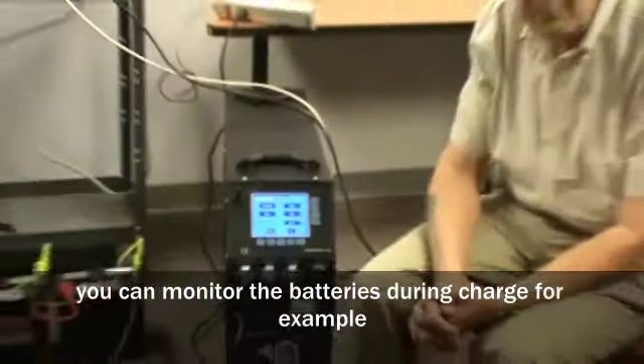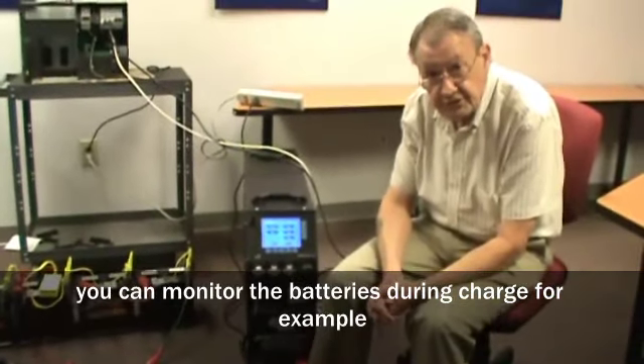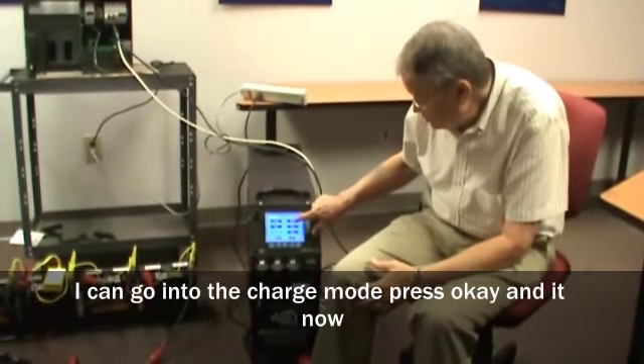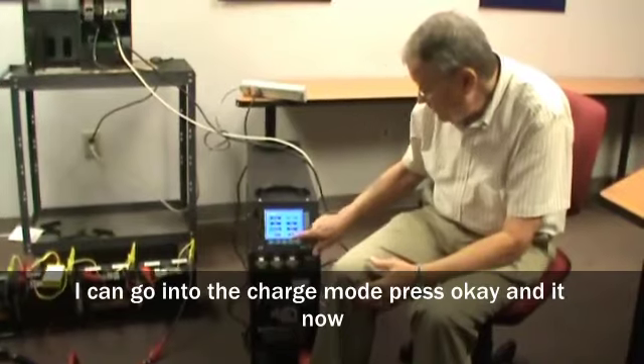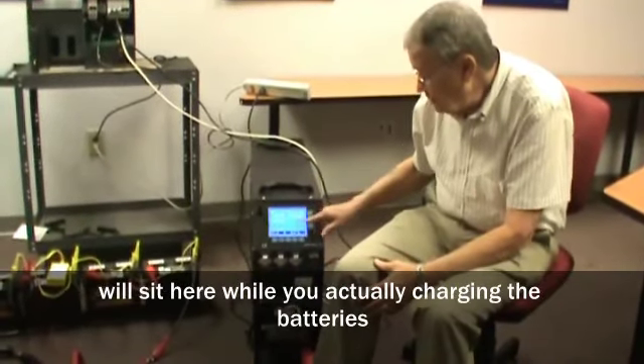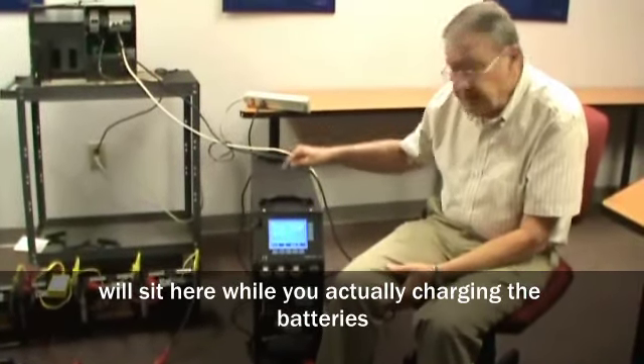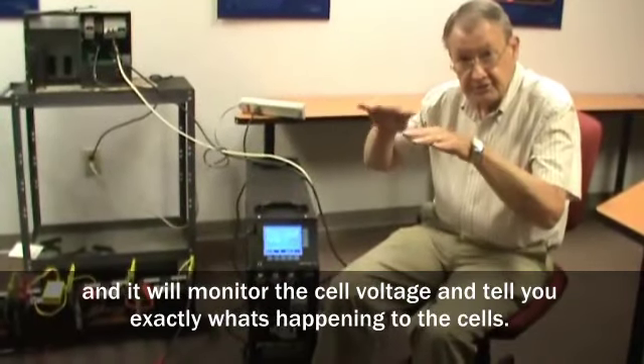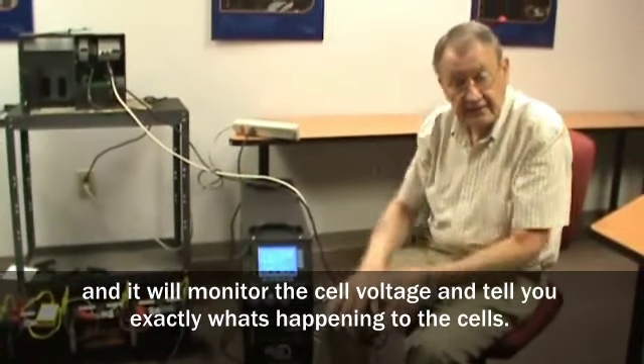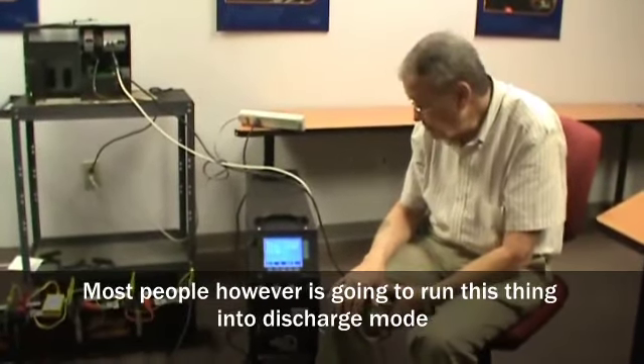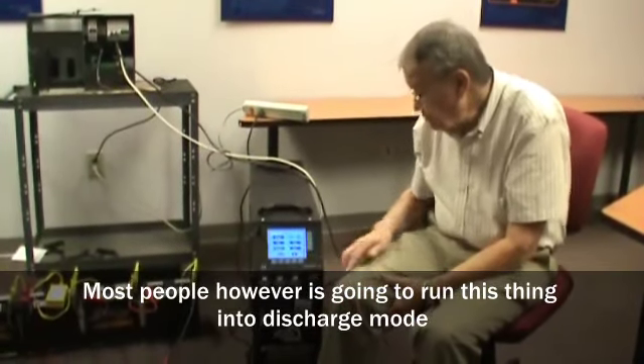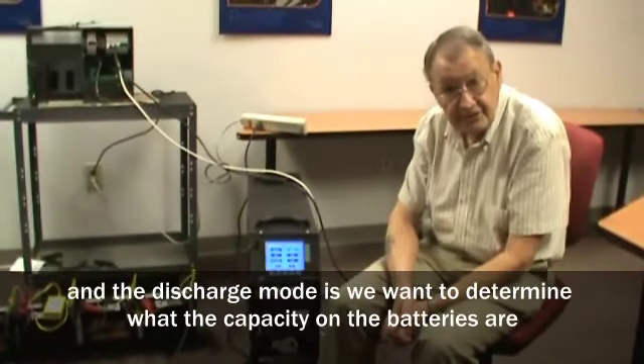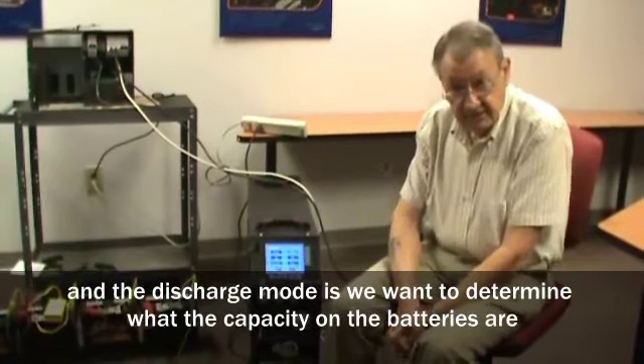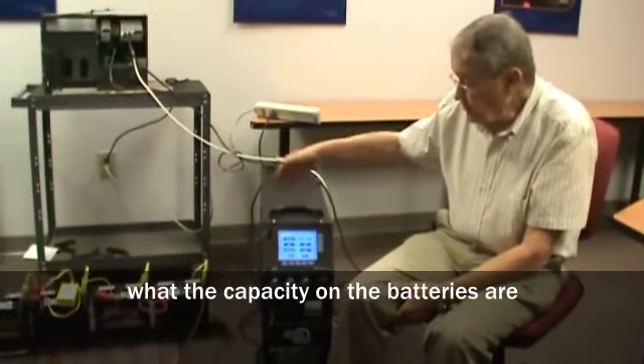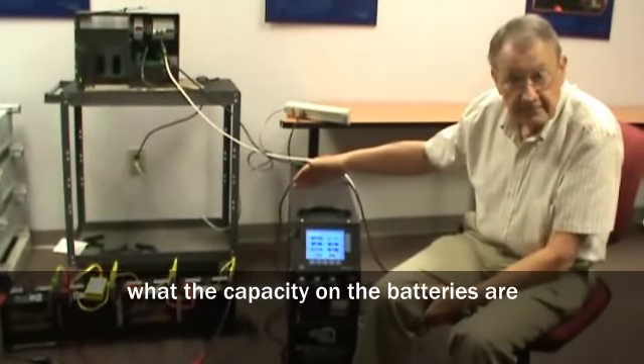You also, and this is another feature of it, can monitor the batteries during charge. For example, I can go into the charge mode, press OK, and it would sit here while you're actually charging the batteries, and it would monitor the cell voltage and tell you exactly what's happening to the cells during charge. Most people, however, are going to run this thing in the discharge mode. And the discharge mode is where we want to determine what the capacity of the batteries are.